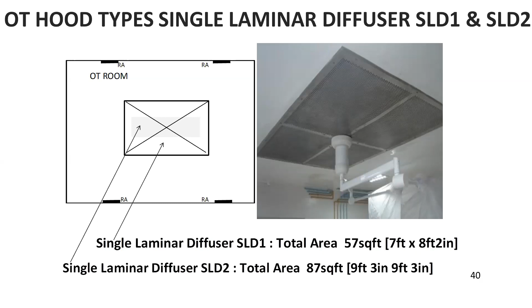Okay, so we are going to talk about, in comparative terms, what is the air quantity, and what is the kilowatts that it consumes. And then what is the CFU per meter cube that you can expect on the OT table. So the air curtain type laminar flow diffuser is going to take 570 CFM. It is so low. It consumes only 0.95 kilowatts for the blower.